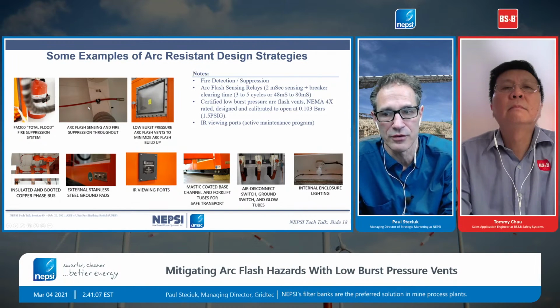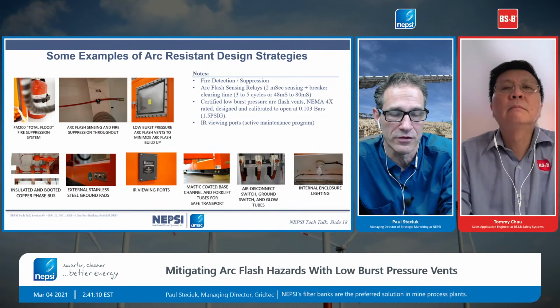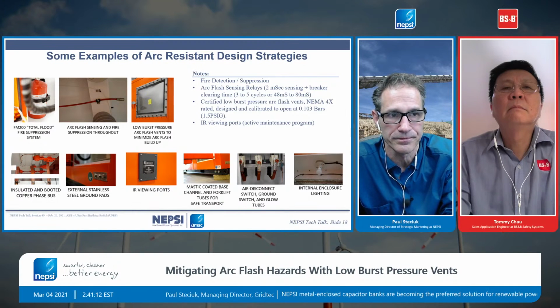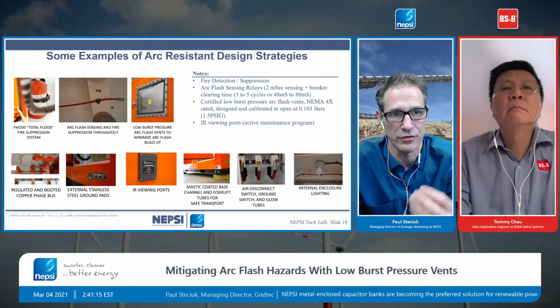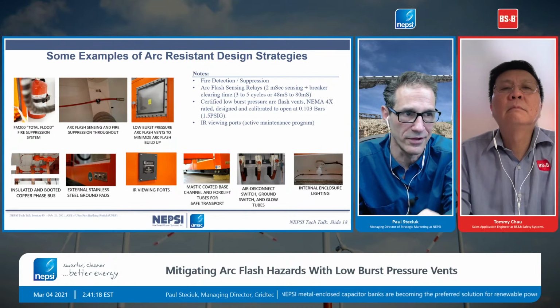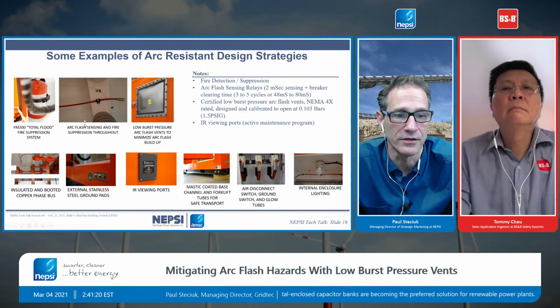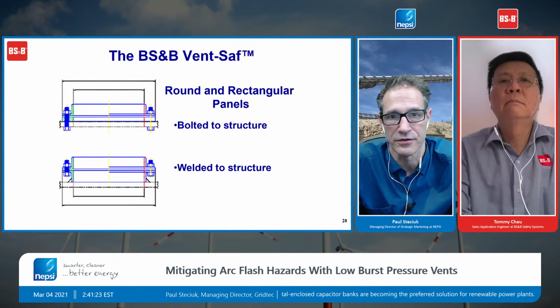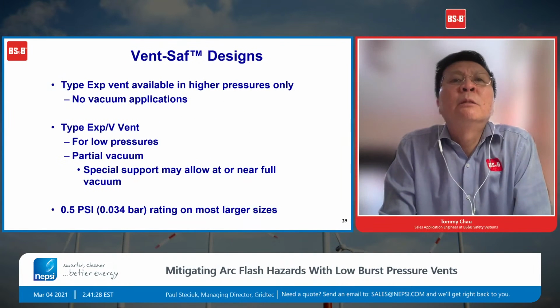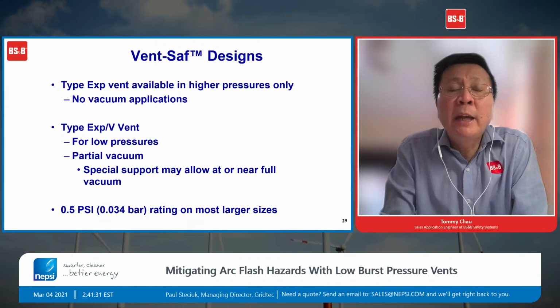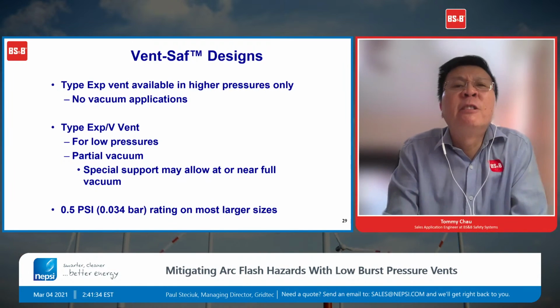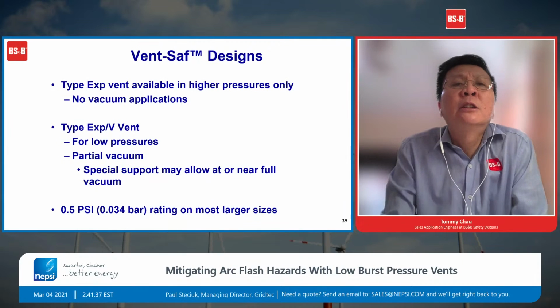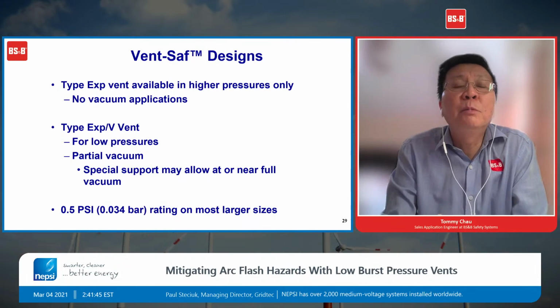So kind of back to the next question, we're trying to prevent faults in the first place. We are doing other things as standard, those low-cost items, and then there's higher-cost items like the vent here that we can often supply. Okay. So again, BSB manufacture different types of panel. We have a name for all of the panels that we provide. So they are low burst pressure membranes, and typically in a lot of our applications, the equipment sees a lot of back pressure and vacuum.